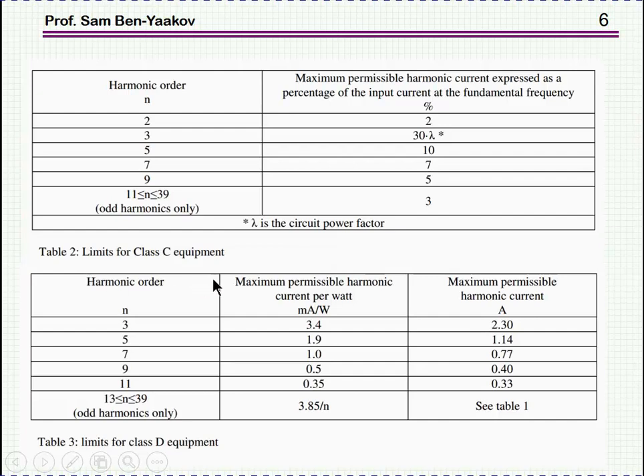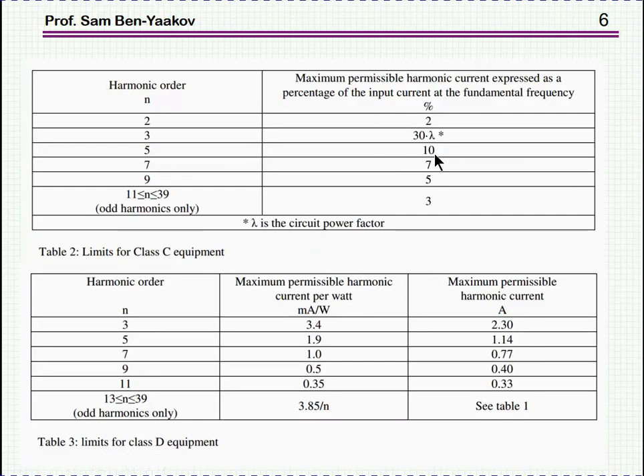This is now for class C. The limits are not defined as absolute currents, but really proportional to the first harmonic. For example, the fifth harmonic is 10% of the first harmonic — the major component of the current — so it's not dependent on the power level. For each power level, it will be 10%. The definition of the third harmonic is odd: it's 30 lambda, where lambda is the circuit power factor. So if the power factor is approaching 1, it will be 30%; if the power factor is 0.5, it will be only 15%.